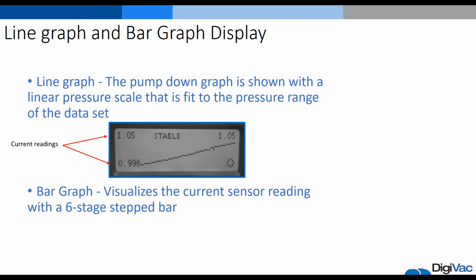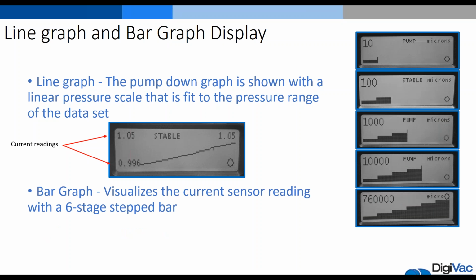And the bar graph visualizes the current sensor readings with a 6-stage step bar graph. So as I brought up on the right-hand side of the screen are the 6-stage steps, but I only displayed 5 of them because it demonstrates the process in the same way. You can see in each stage a new bar is created to see if the system is pumping, if it's stable, or if it's leaking.